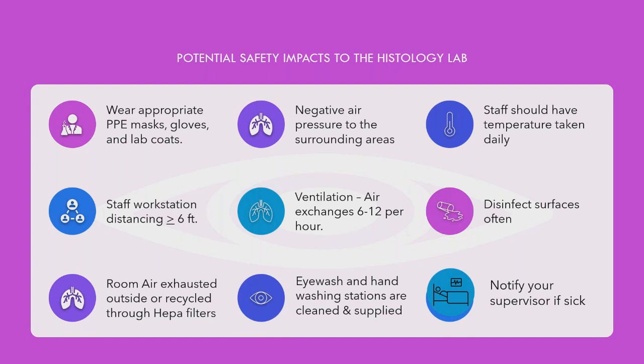Negative air pressure to surrounding areas is true for some laboratories but not all. The ventilation exchanges required for your lab should be between 6 and 12 per hour. Ask your facilities department or supervisor for that number. The higher the exchange rate, the faster air is filtered — reducing your time of exposure if an asymptomatic person is present. This is what airlines are now doing to prevent COVID transmission.